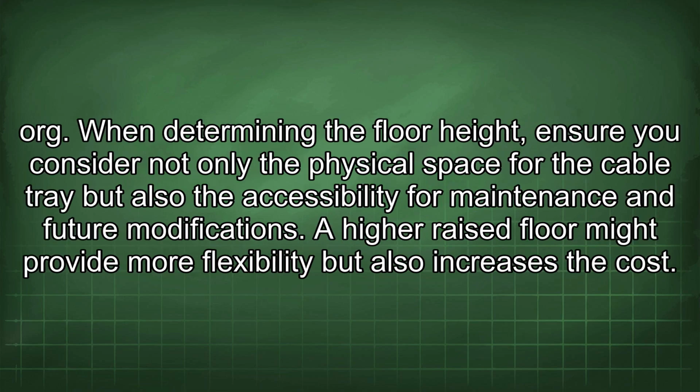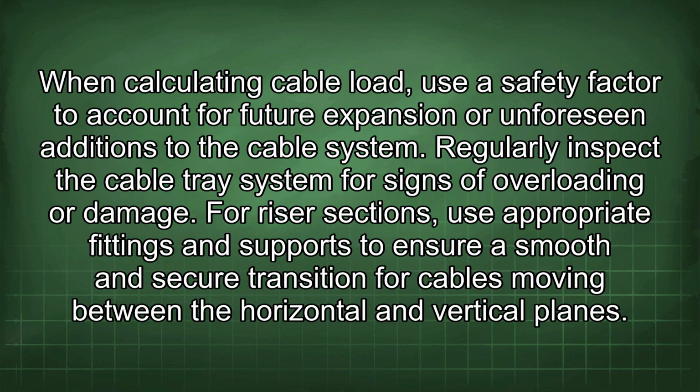When determining the floor height, ensure you consider not only the physical space for the cable tray but also the accessibility for maintenance and future modifications. A higher raised floor might provide more flexibility but also increases the cost. When calculating cable load, use a safety factor to account for future expansion or unforeseen additions to the cable system. Regularly inspect the cable tray system for signs of overloading or damage.